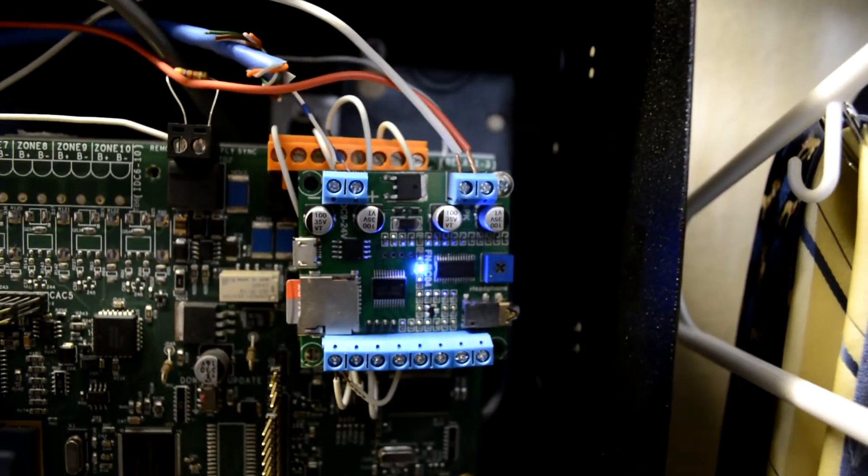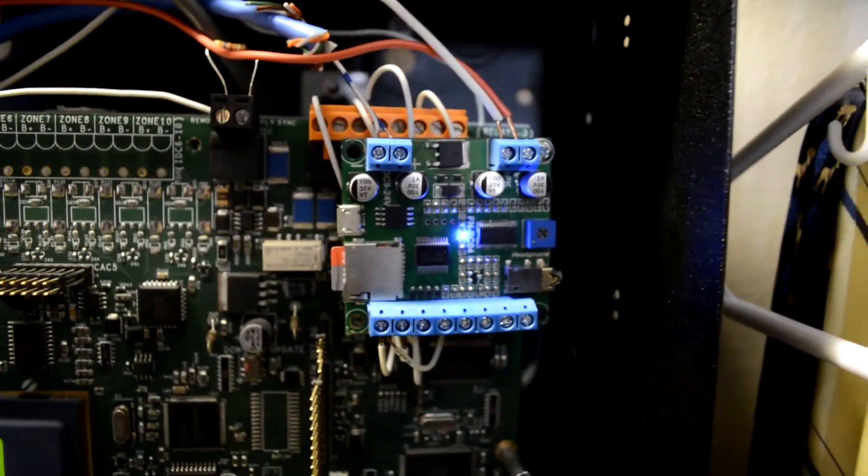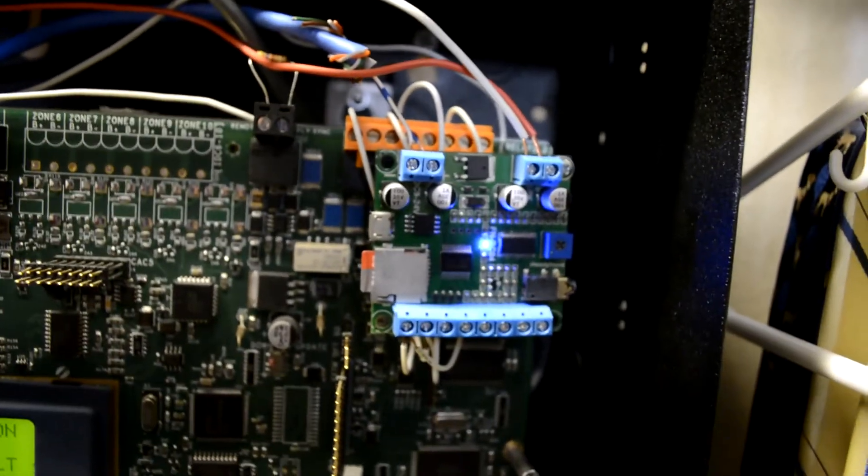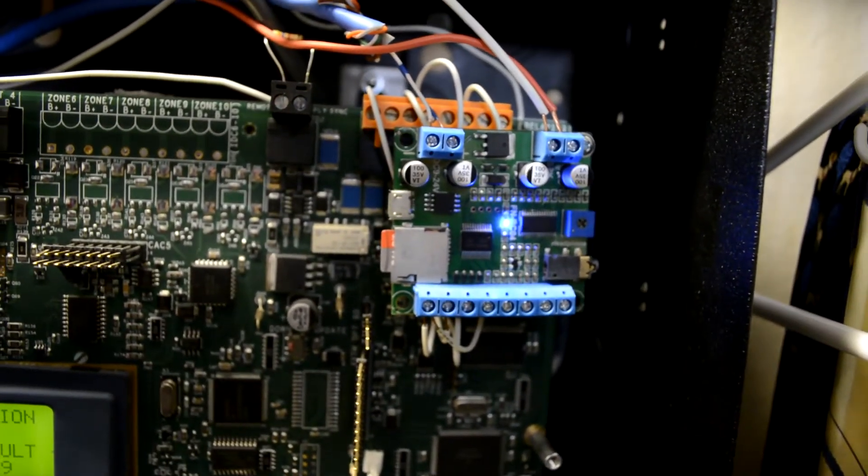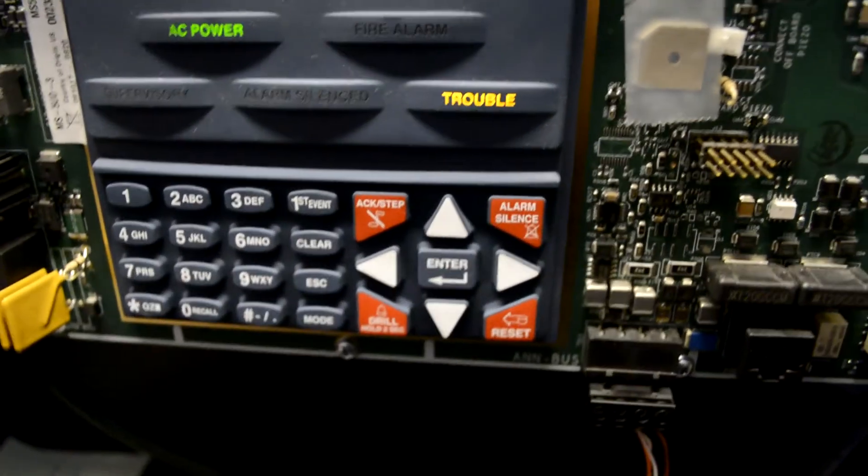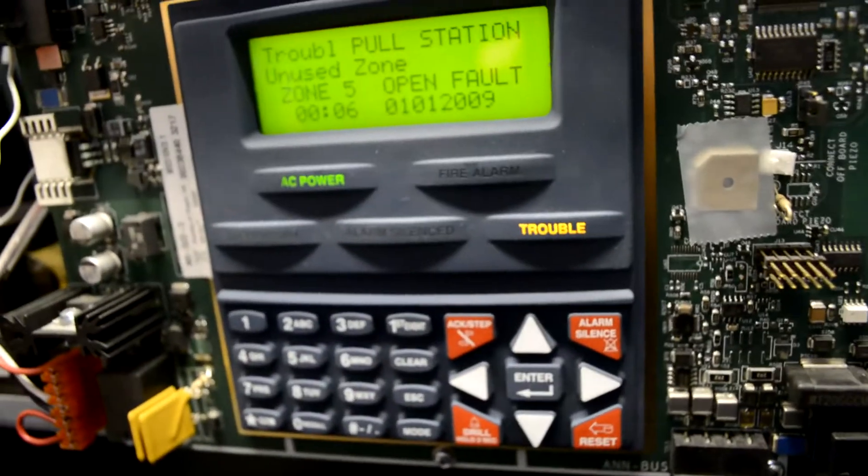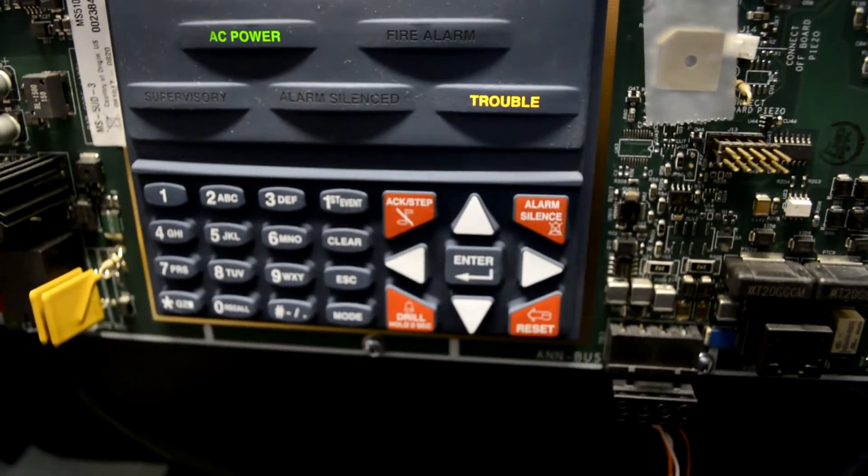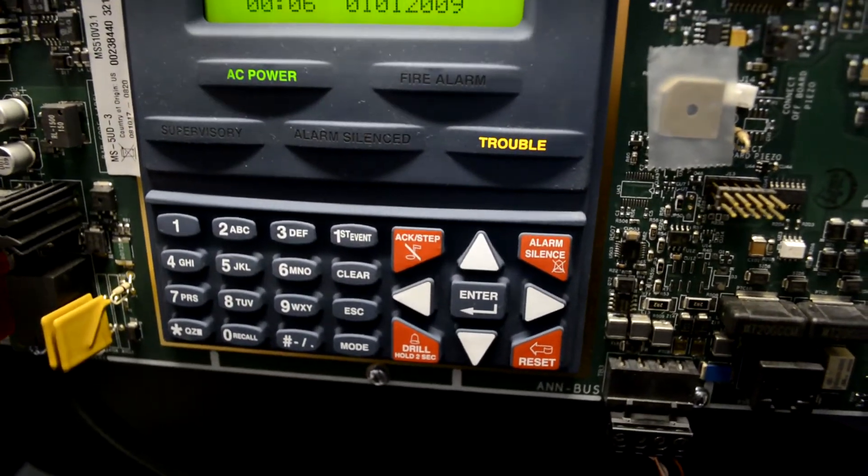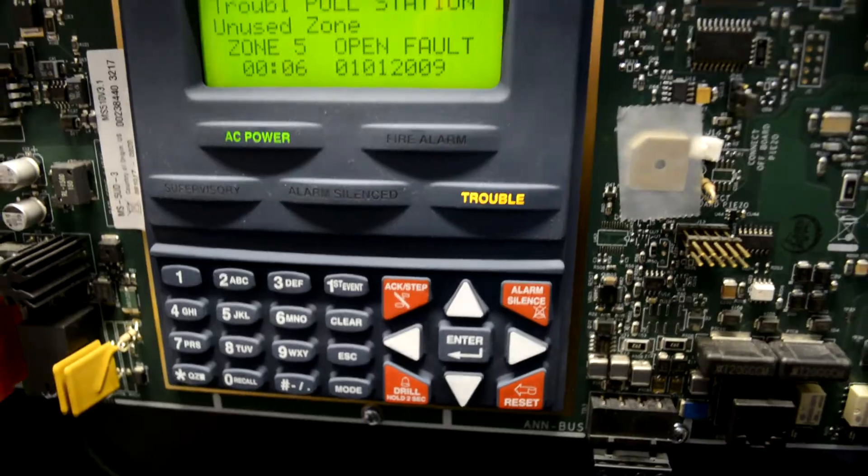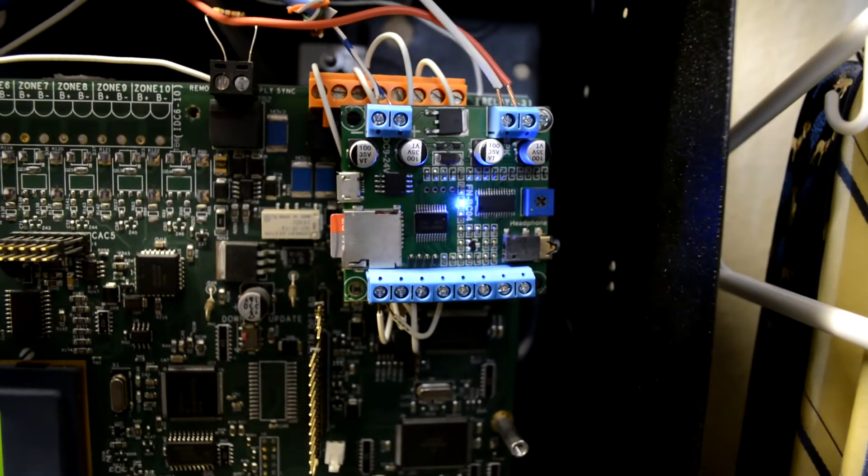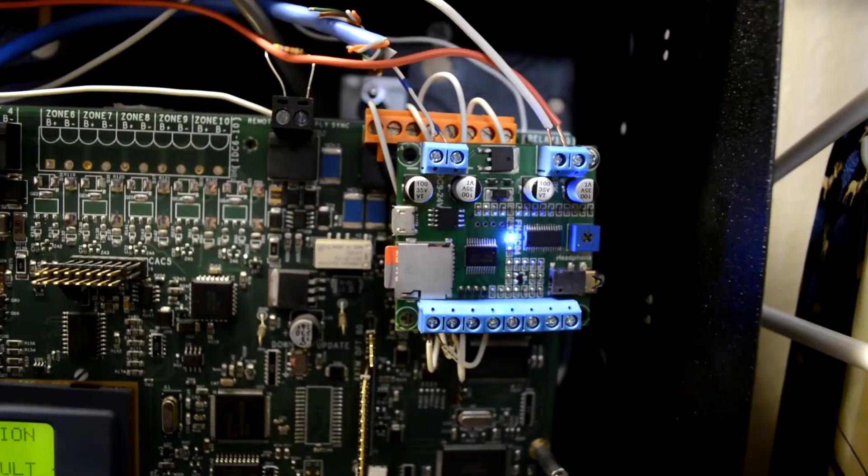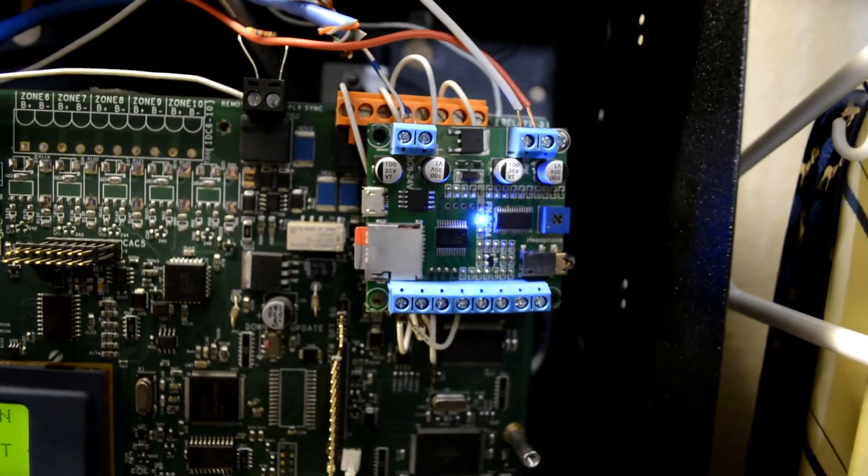The one intriguing thing about this is that the drill function does not activate the alarm relays. So you cannot use the drill function on the panel unless the system has already been put into alarm. If the system is already in alarm and you've silenced and you hit drill, you can reactivate the alarm relay. But if the system is not already in alarm, it's not going to trigger. Let's go back over to the pull station and we'll go ahead and activate.